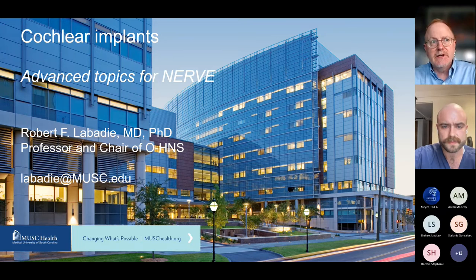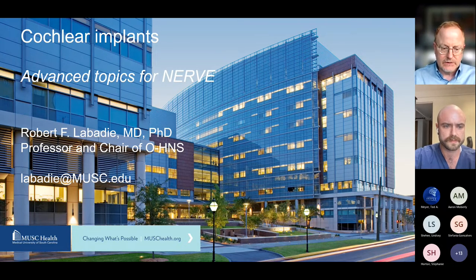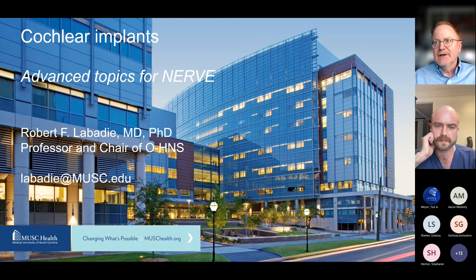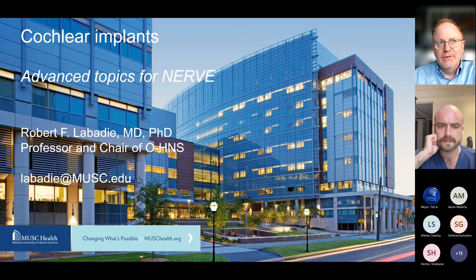The way spread of excitation works is that you stimulate an electrode and then record the response on all the other electrodes. You should essentially see a single peak, where the electrodes closest to that stimulating electrode have the highest electrical charge, diminishing as you move further away. If you have a foldover, you see a double peak, where electrodes in close proximity because they are folded over have essentially the same charge from that stimulating electrode.